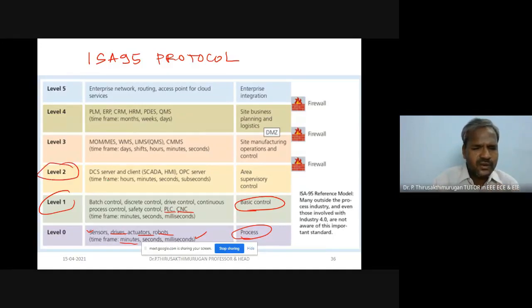Then level 2, DCS server and clients. The DCS server clients are SCADA, HMI, and OPC server, also with time frames of hour, minutes, seconds, milliseconds. This comes under area supervisory control.